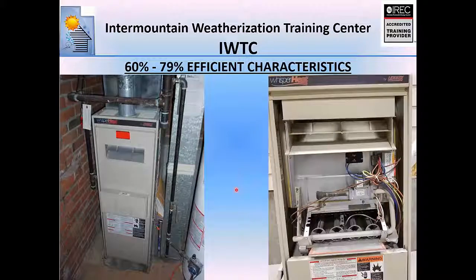So let's start with the 60 to 79% efficiency characteristics. Now this one over here, I pulled the front door off of it so you can see what's going on in there. Again, we've got the draft hood or draft diverter, which allows air from the envelope, or air from the room that it's in, to go into the flue. This is a hole that is a direct connection to the flue. So this can backdraft flue gases right back out of this guy here.